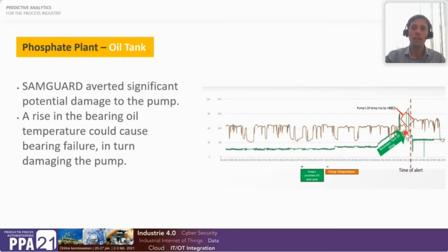Because he put too much oil, the pump could not rotate as it should, and it got heated very fast. If we were not there to alert them, the pump would probably have completely failed and the motor would be destroyed. So again, these are unexpected and unforeseen events - here there was no damage done. They reduced the amount of oil, you can see it in the green measurement, and now everything's fine.